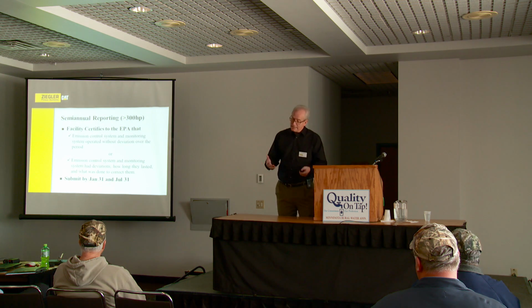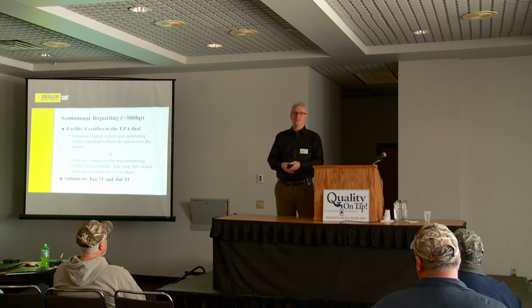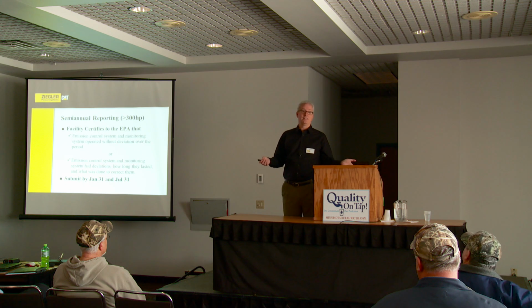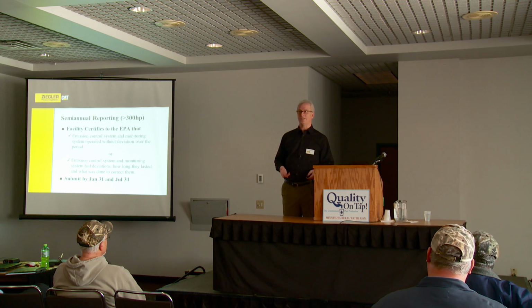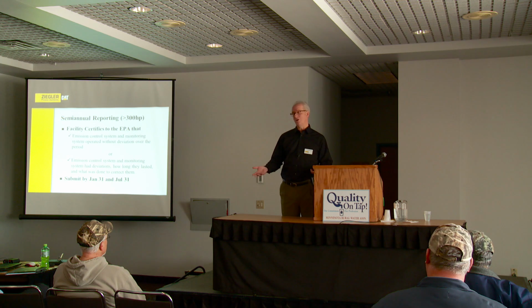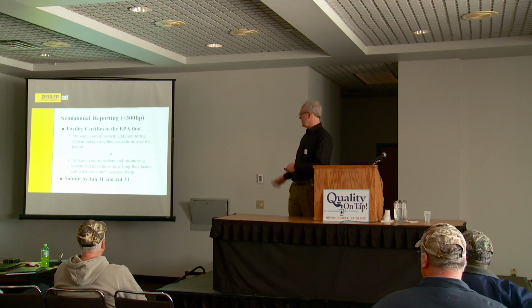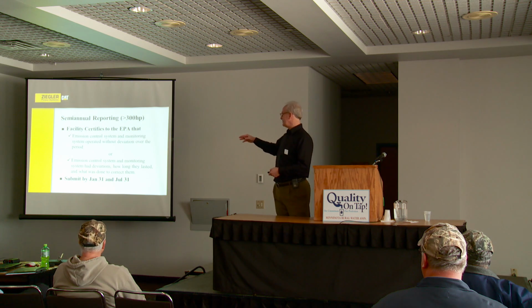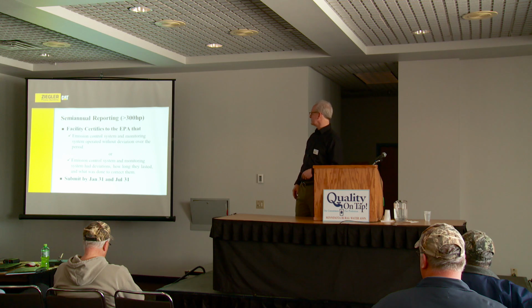And then the EPA wants you to send in notification semi-annually. And there are 2 versions of that notification. One is, I ran for the last 6 months, I didn't have any deviations. The other one is, I ran for the last 6 months, and I had this deviation, and here's what went wrong, and here's how I fixed it. When my temperature sensors failed, I noticed it, I replaced the sensor, and now it runs fine. And those would need to be submitted by January 31st for the previous 6 months or July 31st for the previous 6 months.